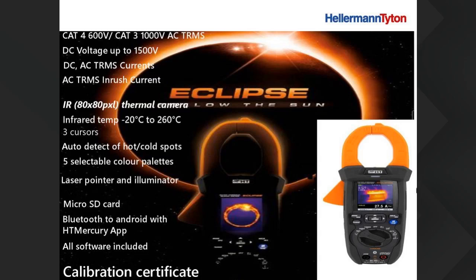First of all, it's a Cat 4 600 volt meter or a Cat 3 1000 volt true RMS voltage meter. And then the plus point of this meter, and it's very unique, is that it can measure DC voltages up to 1500 volts. Now that is specifically for the guys doing solar. The new regulations allow them to measure up to 1500 volts DC with a handheld multimeter. So this meter is one of our first clamp meters that actually has this feature. It can also measure your AC or DC currents. It's an AC-DC meter up to 1000 volts, and it can also measure inrush currents.